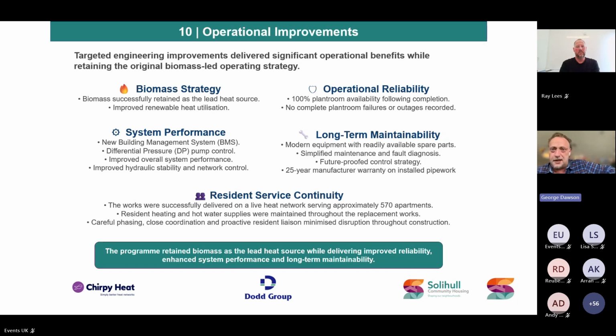Through the installation process, Solihull now have systems with a 25-year manufacturer warranty on the installed pipework, and an ongoing water quality regime as per BSRIA requirements, so we're maintaining the performance and efficiency of the systems on a constant basis. We've got remote connectivity through to the BMS, so if there's any issue or alarm scenario, that's signaled to us via email from the respective energy centres. That said, we've had no unplanned outages since completion of the measures.